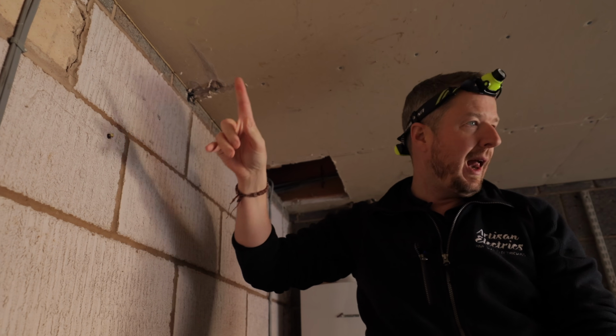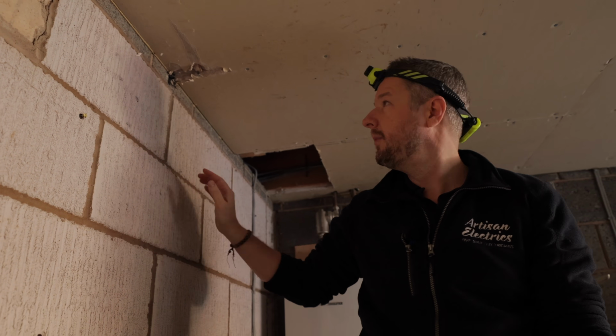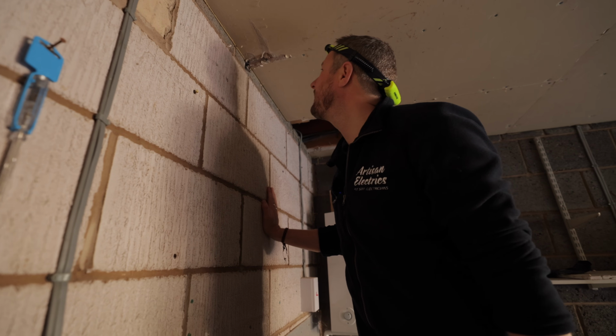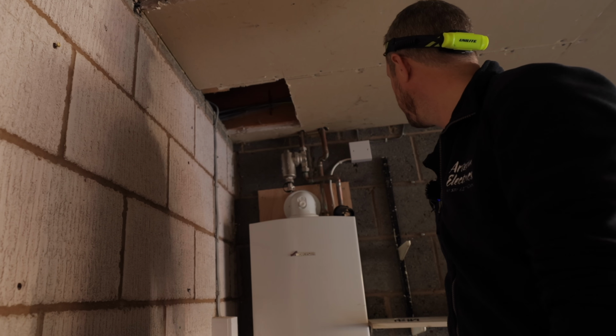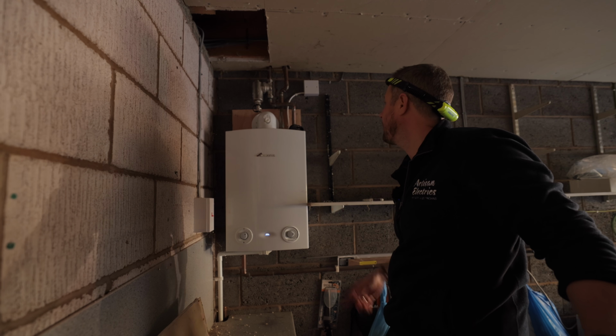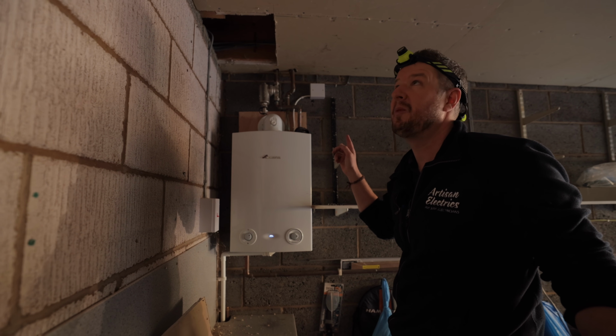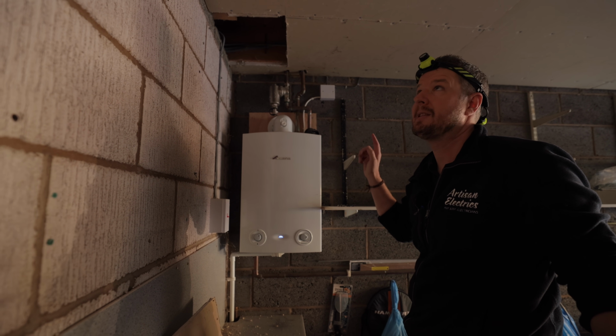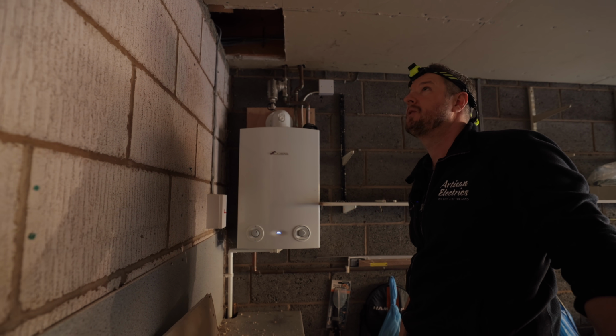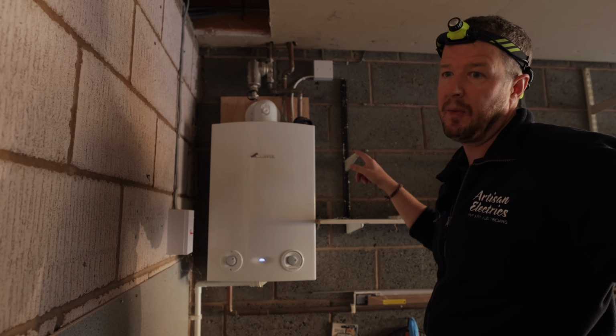What was here before? Was there a light on here or something? We didn't know, I don't know honestly. So we don't know what those do. They do look like lighting cables. Could it be something to do with the boiler maybe? That's something we've experienced before, problems with boilers not being wired up right, and that causing issues. This boiler might actually be on the lighting circuit.